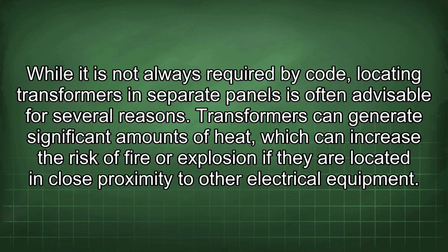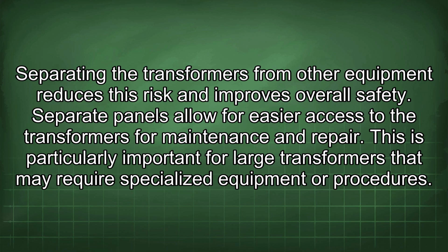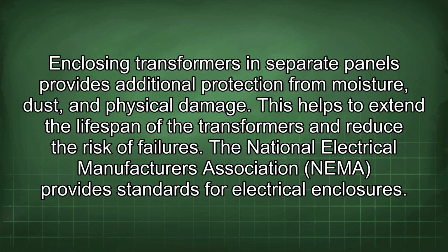While it is not always required by code, locating transformers in separate panels is often advisable for several reasons. Transformers can generate significant amounts of heat, which can increase the risk of fire or explosion if they are located in close proximity to other electrical equipment. Separating the transformers from other equipment reduces this risk and improves overall safety. Separate panels allow for easier access to the transformers for maintenance and repair. This is particularly important for large transformers that may require specialized equipment or procedures. Enclosing transformers in separate panels provides additional protection from moisture, dust, and physical damage. This helps to extend the lifespan of the transformers and reduce the risk of failures.